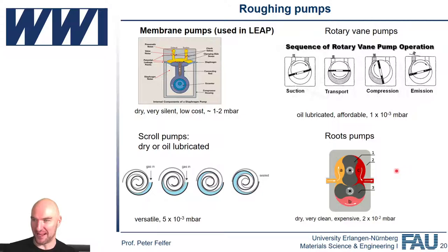The best pump, I personally think, are so-called roots pumps. In a roots pump, you have two pistons that roll on each other, and these two pistons do the compression work. Usually roots pumps can have multiple stages, so you have a bunch of roots pumps behind each other, and the great thing about them is they're dry. So you don't have an oil problem, they're extremely clean, and they get into an extremely good vacuum. Problem is, they're fairly expensive, 5,000 euros maybe, but you can still afford it.